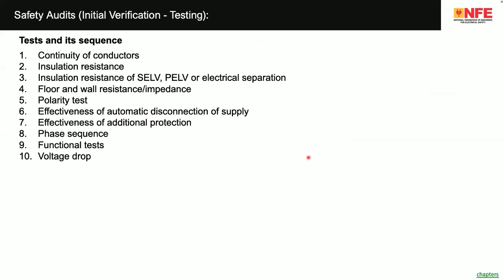Then the other safety measures such as SELV, PELV, and electrical separation are very much applied in medical locations. Floor and wall resistance impedance, polarity test, effectiveness of automatic disconnection, and the last one is voltage drop, and one more, which is PAT, portable appliance test. Please note, the biomedical equipment, frequently or before using, and once when you start using, you are supposed to make a portable appliance test.